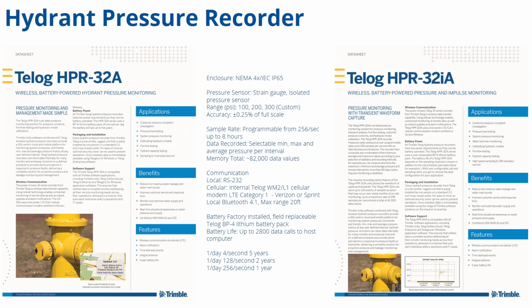But depending on how frequently you sample and how often, possibly if you're using the Verizon or the cellular capabilities, so if you were to sample 4 times per second and make 1 cellular data call a day, it can last up to 5 years. But if you want to set the recorder to sample at its highest data capture rate of 256 times per second, it usually lasts around a year. So the battery life is typically between 1 to 5 years. So this is a very long time for a piece of electronics that's working outside to last. But it is dependent upon how frequent or how high of resolution of data that you want to be able to capture.